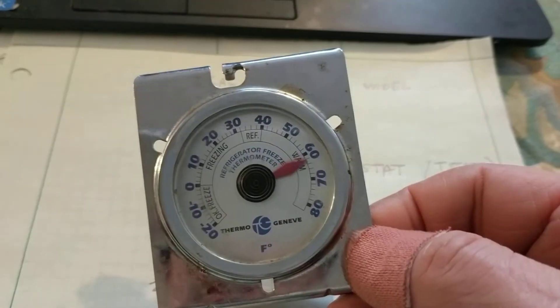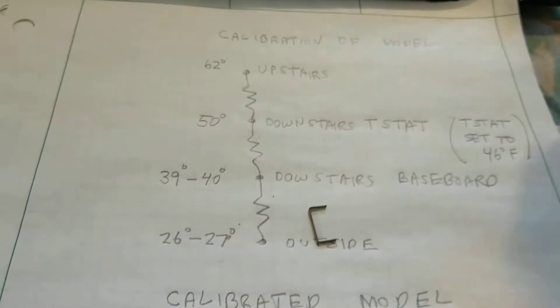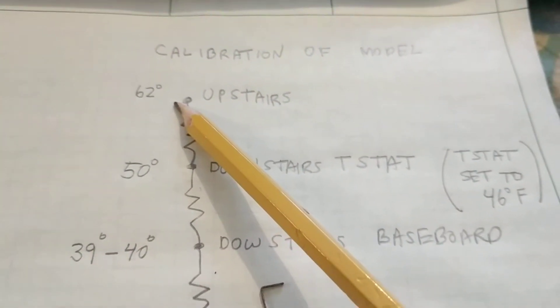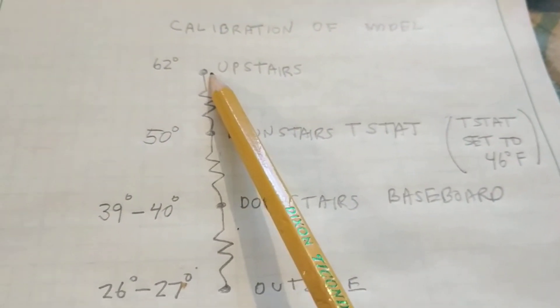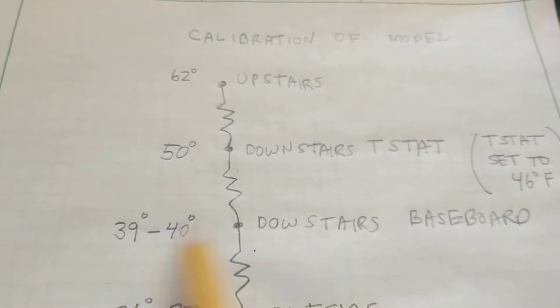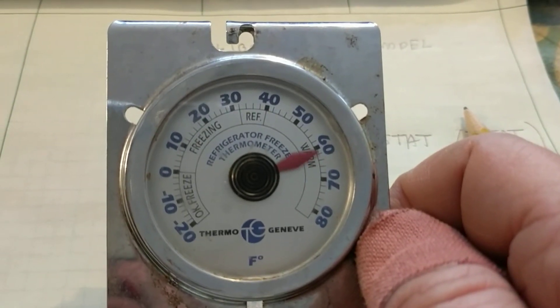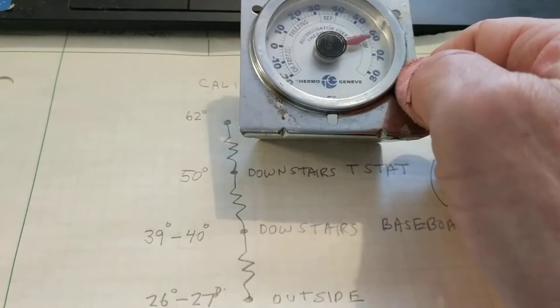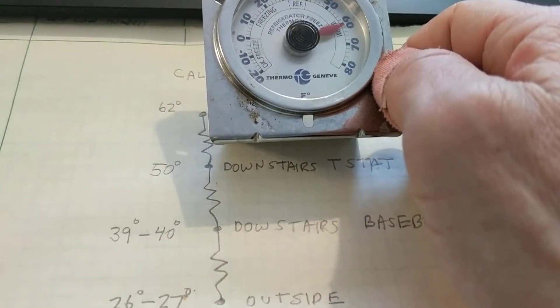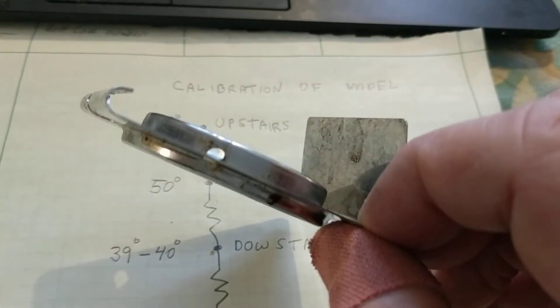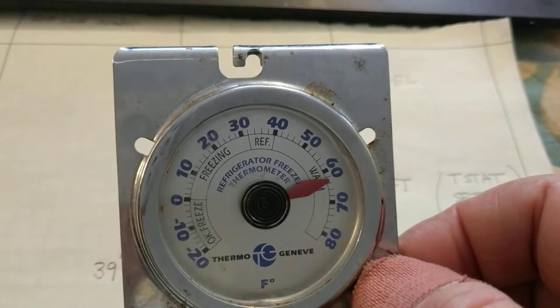The downstairs baseboard was measured with a portable refrigerator thermometer, since there's normally no thermometer there. The other temperatures come from the built-in thermostats. There's some error because this thermometer isn't perfectly calibrated — ideally you'd place it next to the upstairs thermometer and note any offset. Both are metal-coil thermometers with 2-degree gradations, so accuracy is limited to about 1 degree. For this demonstration we'll say the baseboard is between 39 and 40 degrees.